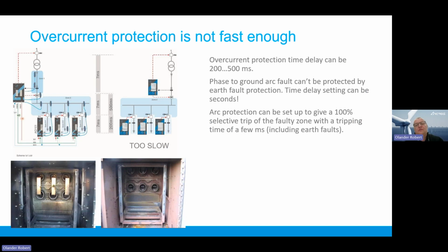And okay, why do you need arc protection? Of course, it's quite clear that if you have a typical overcurrent protection, I will show you a video soon, it's enough if you have a normal short circuit. But if you have an arc flashover in your system, you need to be much faster than 200 milliseconds. It will destroy your switchgear, and it will also be quite dangerous for people working there. So by installing an arc protection system, you can bring this time down to 6-7 milliseconds, including breaker time. Or if you also install a quenching device, you can take the total arcing time down to 4 milliseconds, which is recommended in case you have more than 30 kiloamps of current.